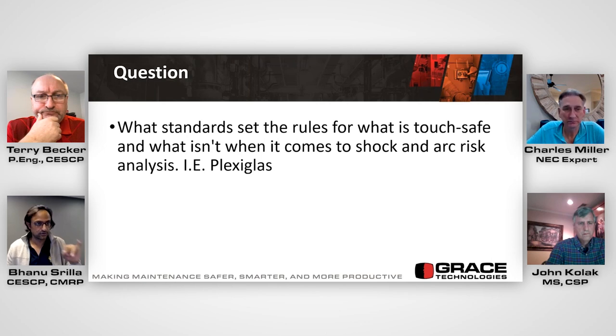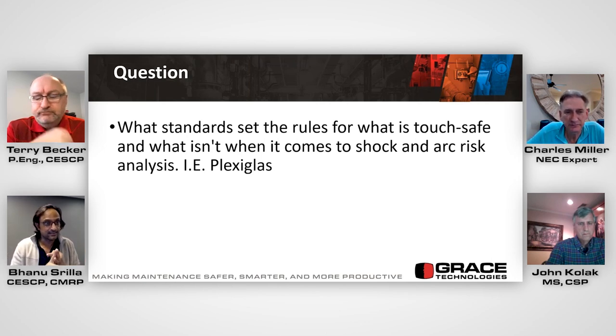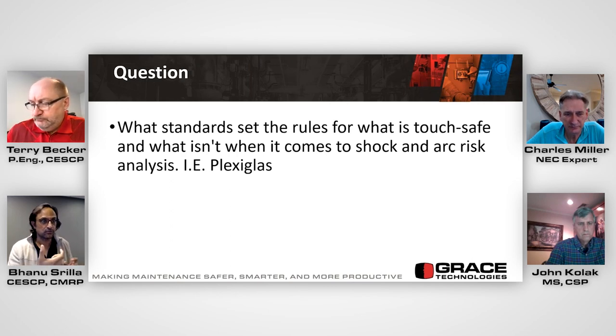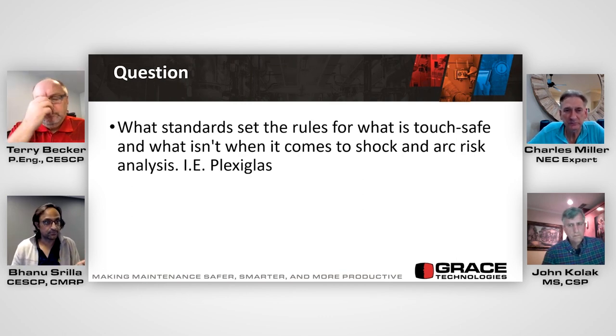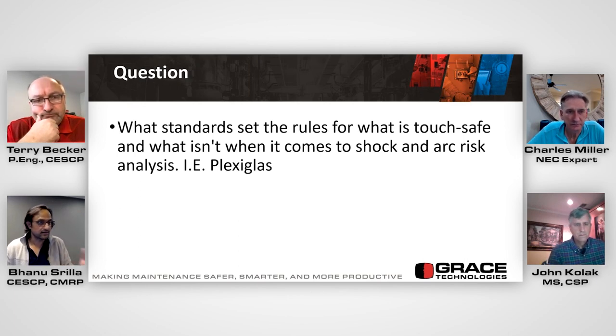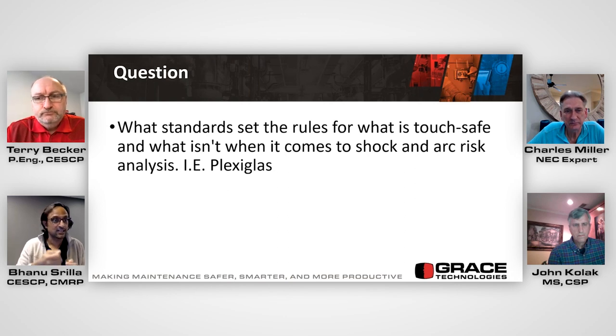That point absolutely needs probes rated Cat 3 or Cat 4. But at the safe test point, since we limit the current to 3.5 milliamps or less, and since you're not directly exposed to transient voltages there, that's different. This test point is tested within UL to take up to Cat 4 ratings, which is a 7300 volt requirement for transient impulses, so you don't have any exposure to Cat 4 transient pulses at the door when you use it.